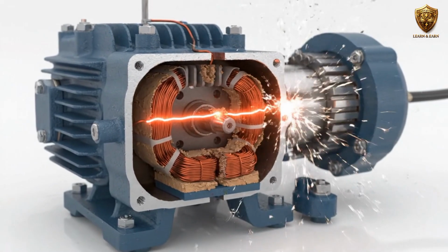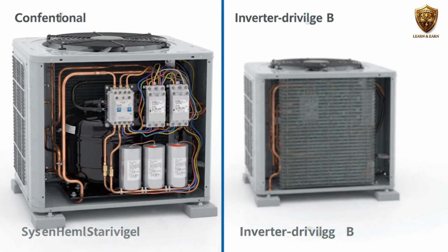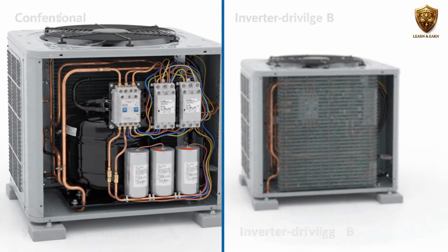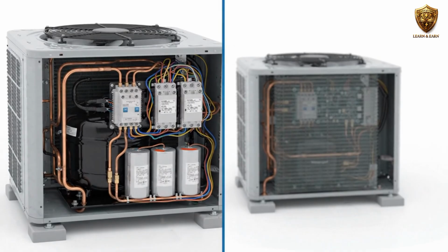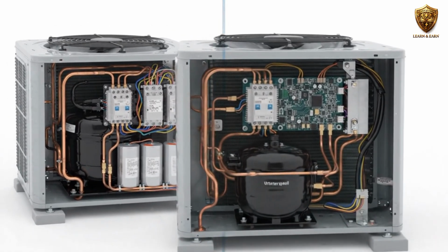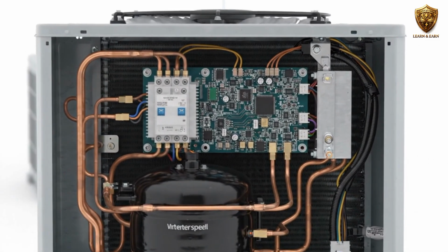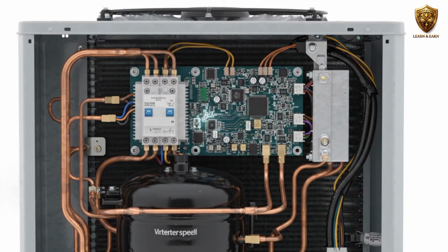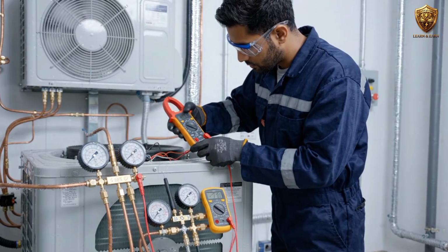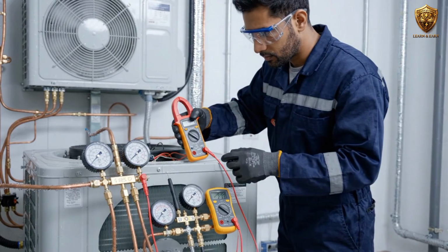For technicians working with inverter systems, compressor diagnosis can be different because the compressor may be driven by an electronic inverter rather than a conventional contactor and capacitor arrangement. Manufacturer-specific procedures become especially important there. The goal is not to memorize one test for every compressor. The goal is to understand what the compressor needs to operate and then verify each requirement safely and logically. The fastest technicians are not the ones who replace parts the fastest. They are the ones who find the fault with the fewest unnecessary steps.